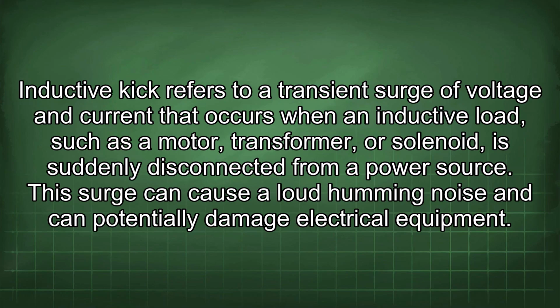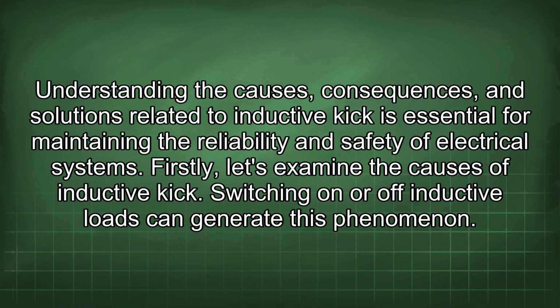Inductive kick refers to a transient surge of voltage and current that occurs when an inductive load, such as a motor, transformer, or solenoid, is suddenly disconnected from a power source. This surge can cause a loud humming noise and can potentially damage electrical equipment. Understanding the causes, consequences, and solutions related to inductive kick is essential for maintaining the reliability and safety of electrical systems. Firstly, let's examine the causes of inductive kick.